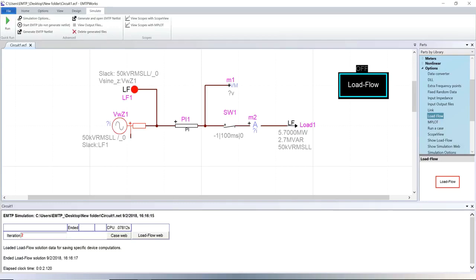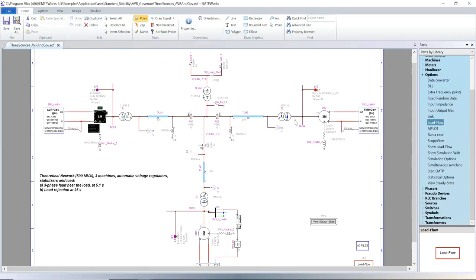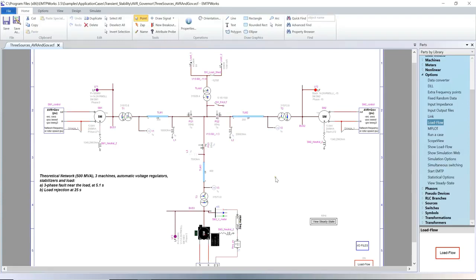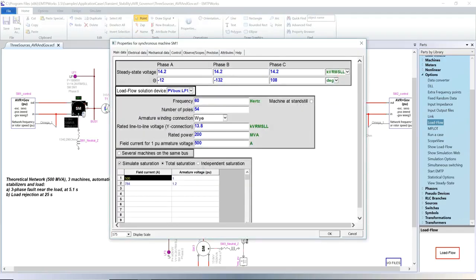Before finishing this tutorial, let's have a look at a case with synchronous machines. Here, three synchronous machines are present. Synchronous machines are typically represented as PV load flow buses. In the synchronous machine mask, link the machine to the load flow previously connected to its terminal.